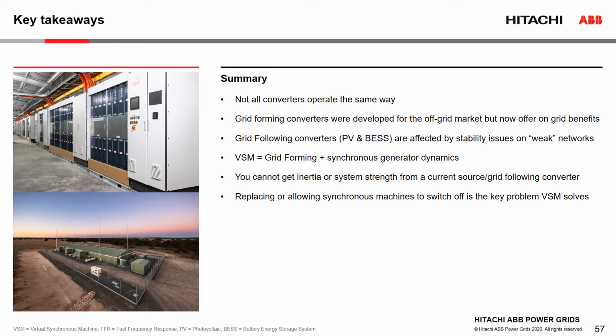So in summary, not all converters operate in the same way. It's important not to broadly categorize all power electronics as having the same challenges. Grid-forming converters were developed for the off-grid market, but now offer on-grid benefits. Grid-following converters, PV and energy storage, are affected by stability issues on weak networks. Virtual synchronous machines are just grid-forming converters plus the dynamic behavior of a synchronous generator. You cannot get inertia or system strength from a current source or grid-following converter, and replacing or allowing synchronous machines to switch off is the key problem grid-forming converters or virtual synchronous machines solve.